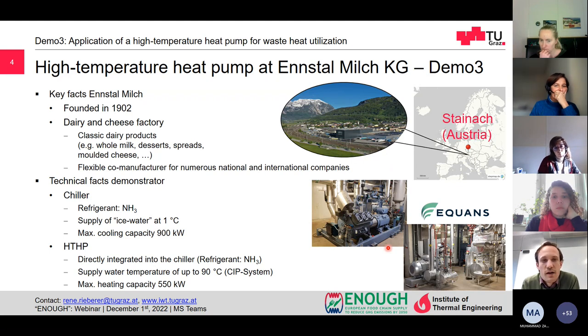ammonia, NH3, and this supplies ice water at around 1 degree Celsius with a maximum cooling capacity of 900 kilowatt. And directly into this chiller, a high temperature heat pump has been integrated by their project partner Equans, formerly ENGIE, which supplies water at a temperature of around 90 degrees Celsius, which is suitable for a cleaning in place system and has a maximum heating capacity of approximately 550 kilowatts.